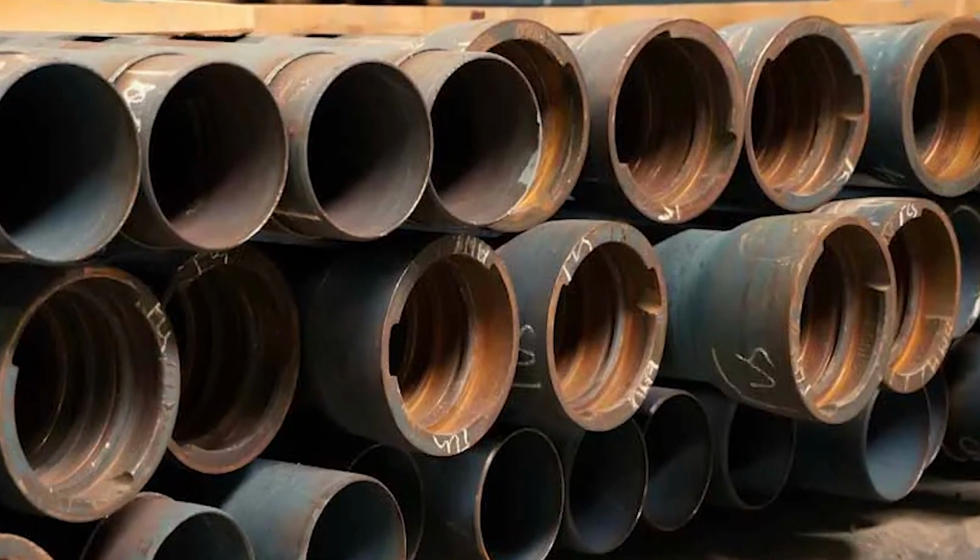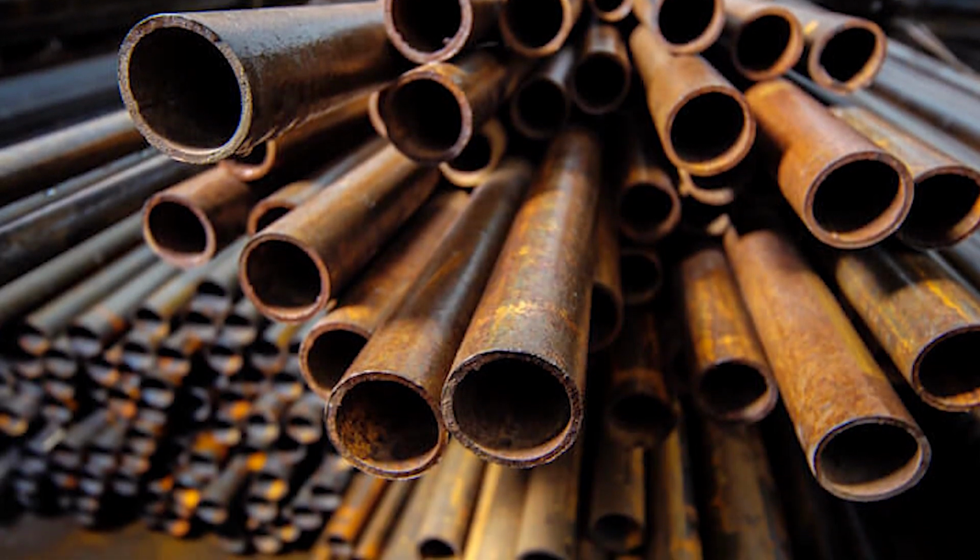And then on cast iron, those came in 10-foot sections. It lasted a little longer. Seems to be about a 60-year lifespan on them. But what happens to cast iron is it rusts away. So a plumbing term is channel rot. The water in a drain system doesn't hold full capacity. Drain just stays really on the bottom of the pipe. So whenever we run our camera through a drain system, we'll see that the bottom of that pipe is actually rotted out, and that water is just surfing on the clay, the Texas clay, or the dirt underneath it. It's still a cylinder, but that whole bottom's rotted out.